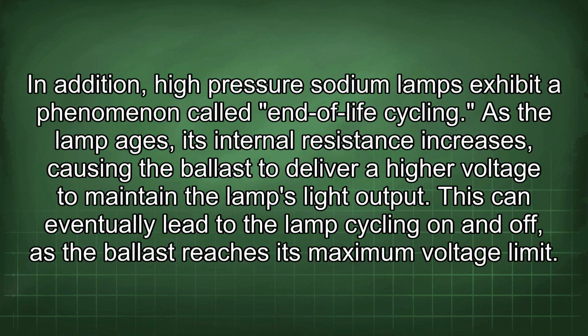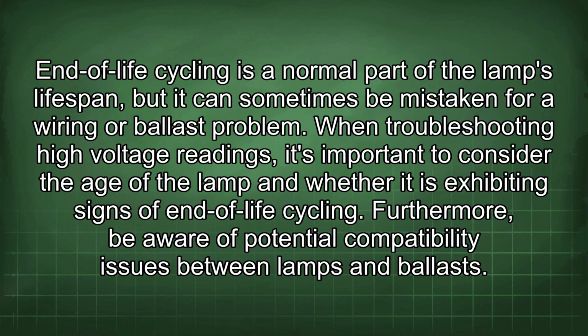In addition, high-pressure sodium lamps exhibit a phenomenon called end-of-life cycling. As the lamp ages, its internal resistance increases, causing the ballast to deliver a high voltage to maintain the lamp's light output. This can eventually lead to the lamp cycling on and off as the ballast reaches its maximum voltage limit. End-of-life cycling is a normal part of the lamp's lifespan, but it can sometimes be mistaken for a wiring or ballast problem. When troubleshooting high voltage readings, it's important to consider the age of the lamp and whether it is exhibiting signs of end-of-life cycling.